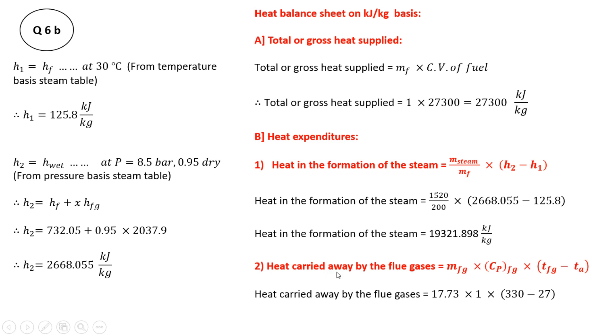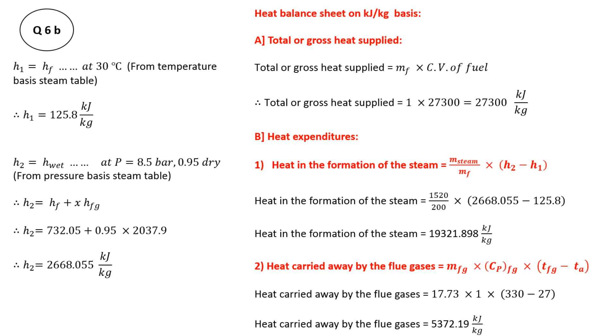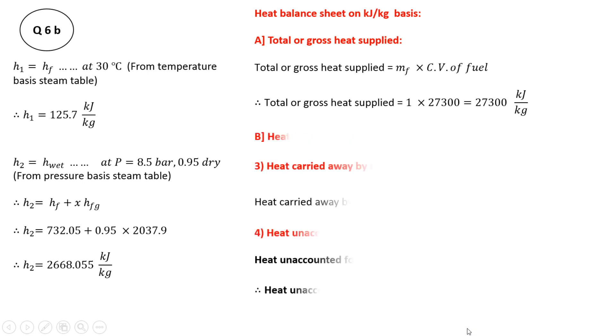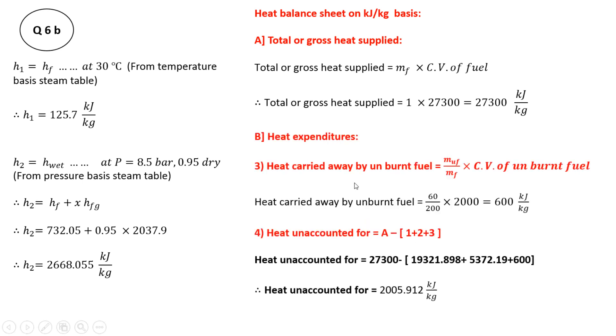Next, we find the heat carried away by the flue gases using Q = m·cp·ΔT. Mass of flue gases is already given per kg of fuel burned as 17.73 kg, cp of flue gases is 1 kJ/kg·K, and temperature difference is (330 − 27) = 303°C. So heat carried away by flue gases = 17.73 × 1 × 303 = 5372.19 kJ/kg.